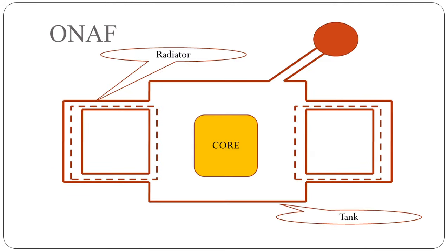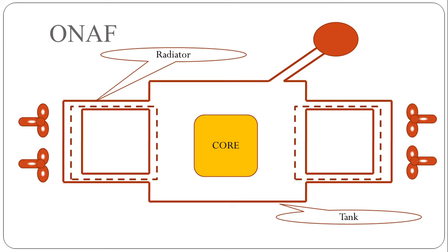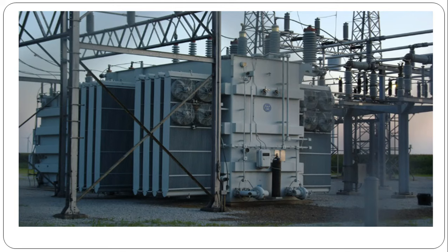In this transformer, oil natural air natural cooling is the base, but if we use fans for enhancement of cooling then it becomes oil natural air forced cooling. In this practical transformer you can see that the radiators are connected to the tank. Fans are used to force air through the radiators, enhancing the cooling of transformer oil. This is ONAF — oil natural air forced cooling.